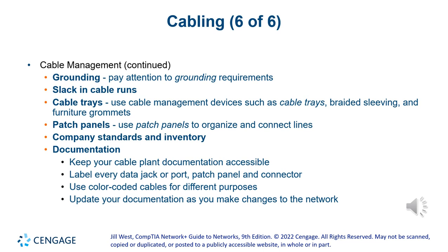Also, I mentioned before the grounding. Grounding is really important. You need to make sure that everything is grounded. Your equipment has the proper grounding, and the proper grounding has to be connected to the FPL grounding. At the Kendall campus, we did not have a proper grounding. We had to bring electricians so they could call FPL. FPL came and gave us a point that says, yeah, here is our ground reference point.